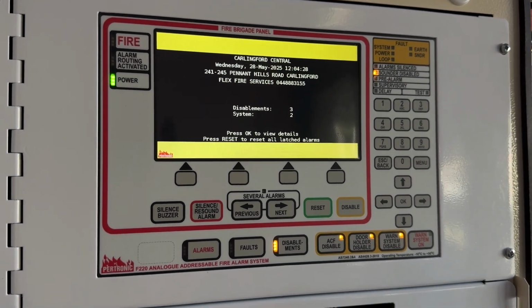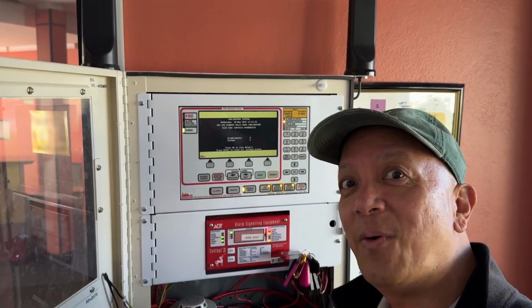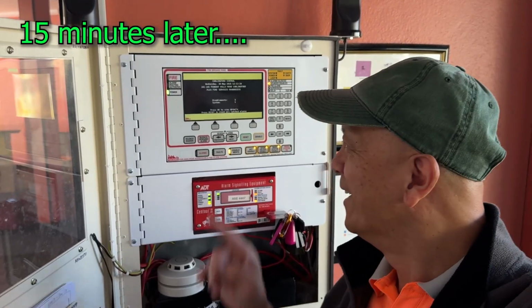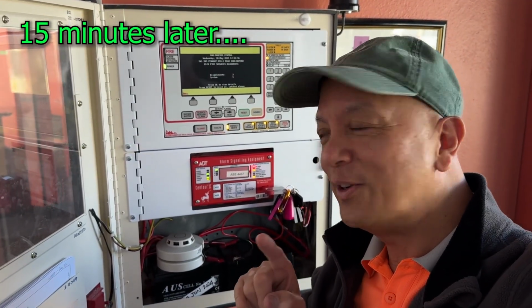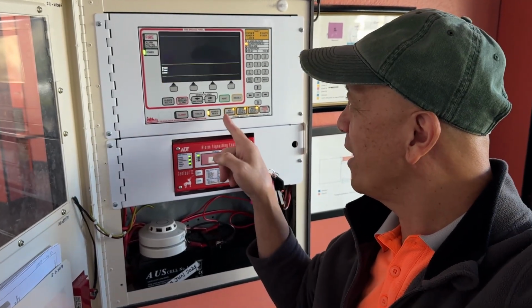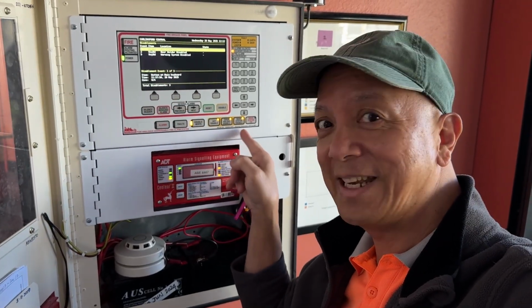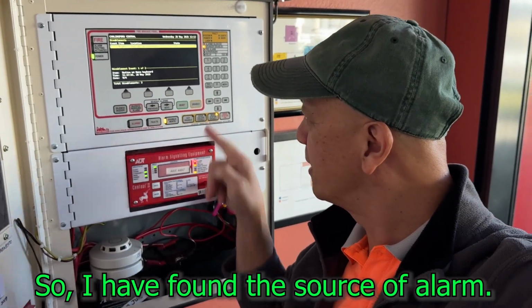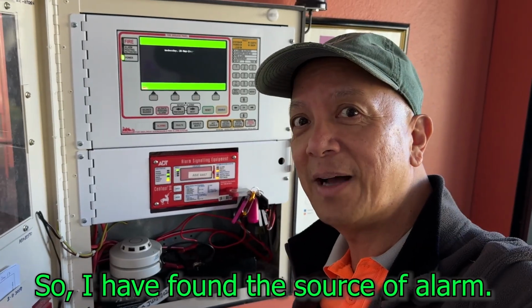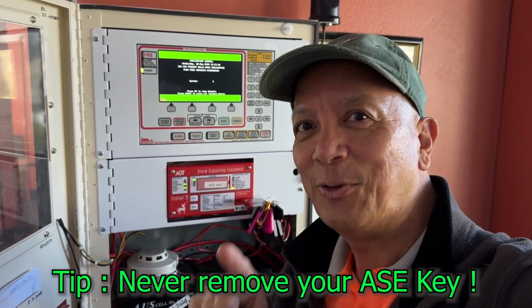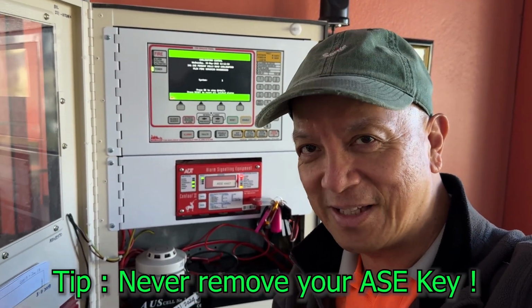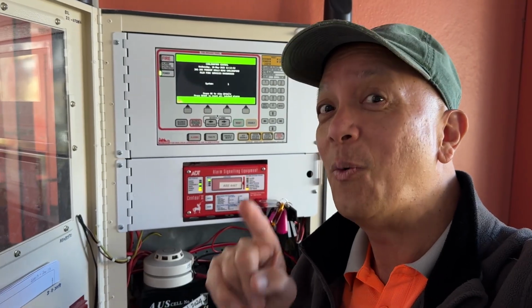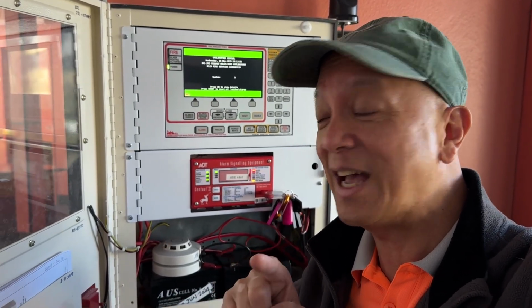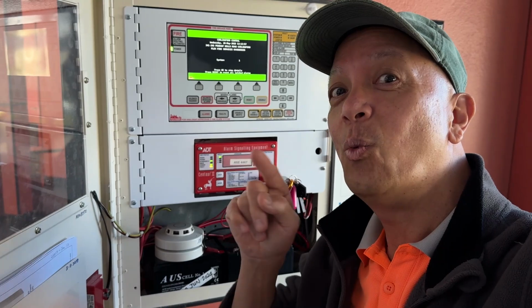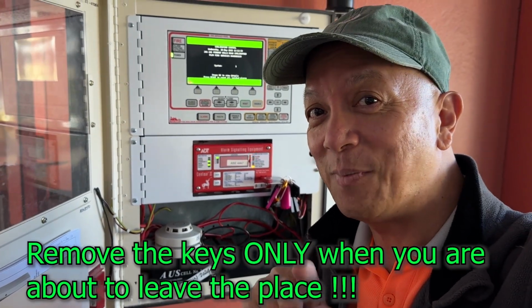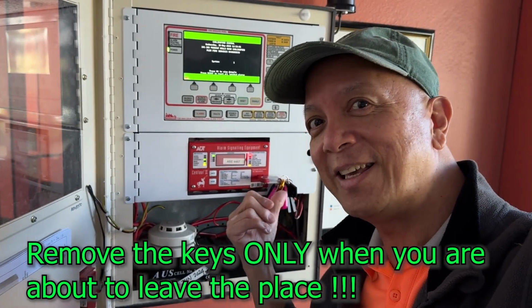Okay, we're going to stay here for a while. It's been more than 15 minutes. The alarm never returns. So the disablement we have is 1, 2, 3. I'm going to put that to normal. So the system is now back to normal. Take note, do your paperwork, do not leave the site. Once you finish, and you're about to go to your car, that's the time you remove your ASE. While you are on site, this is my tip: never remove your ASE key.